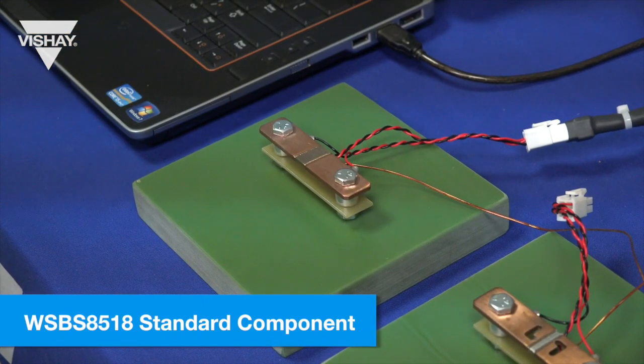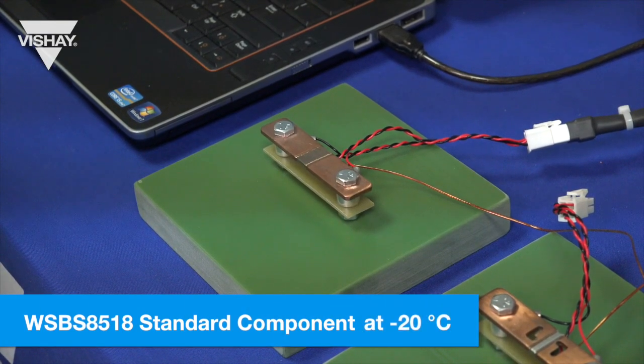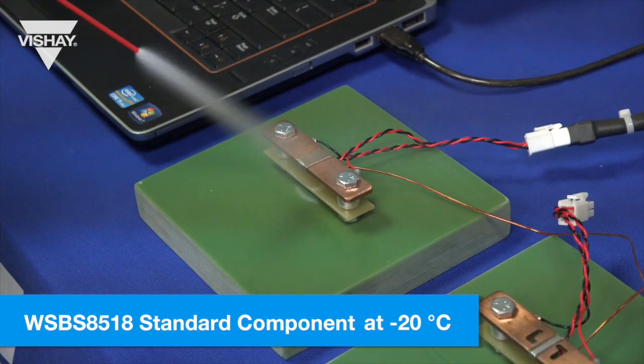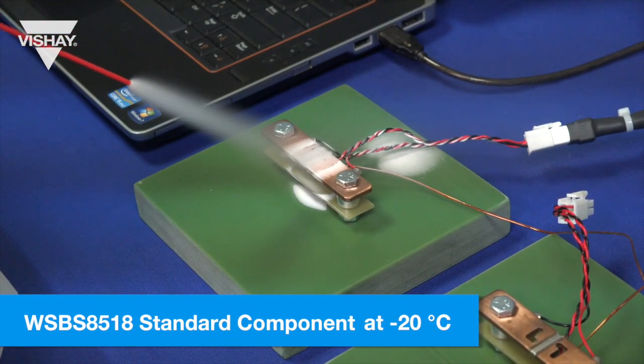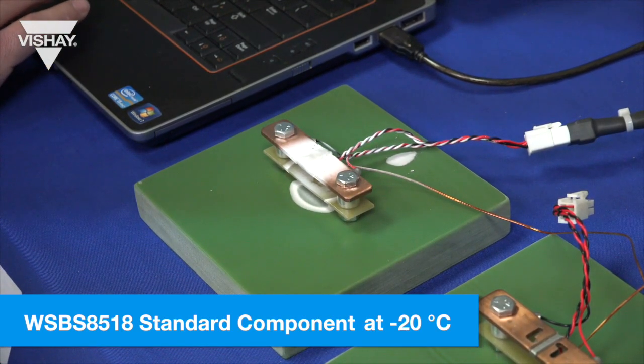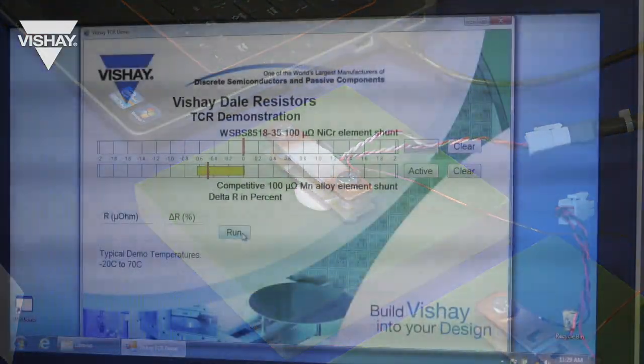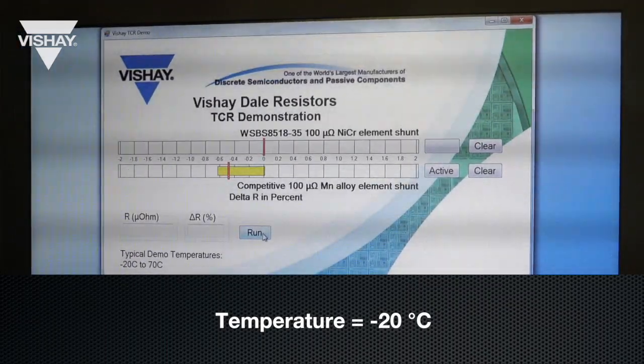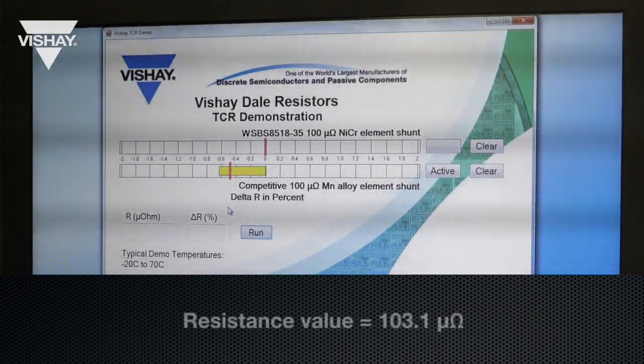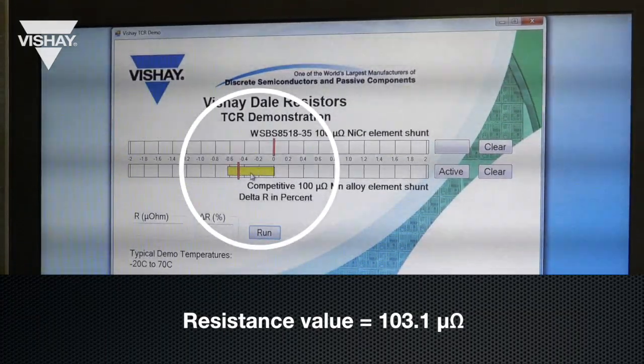To first prove the TCR performance we're going to do a test at around negative 20 degrees C. I will hit the WSBS 8518 with cold spray until it gets the resistive element temperature to minus 20 degrees C. Now it's at that temperature, we will run the test and it'll chart the resistance reading, which is about 103.1 micro-ohms. The resistance value was around 103.1 micro-ohms and you can see the chart and the change of resistance.